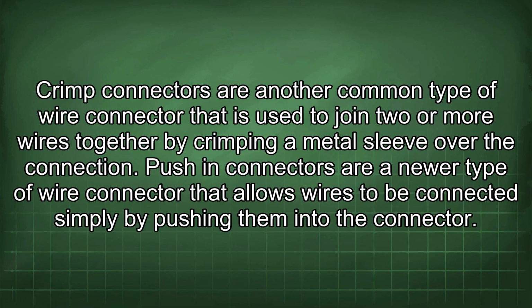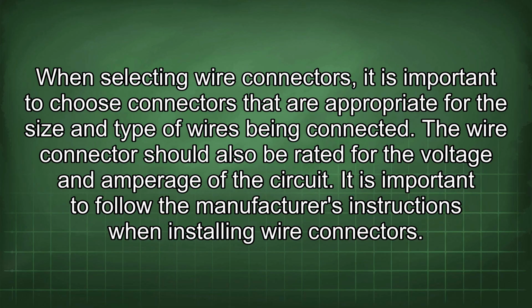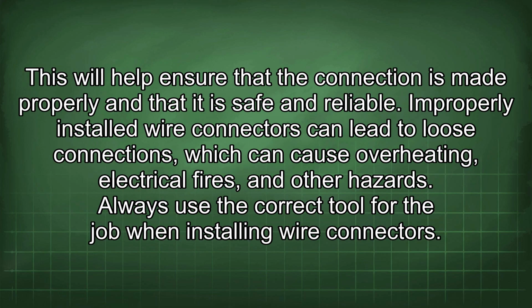When selecting wire connectors, it is important to choose connectors that are appropriate for the size and type of wires being connected. The wire connector should also be rated for the voltage and amperage of the circuit. It is important to follow the manufacturer's instructions when installing wire connectors. This will help ensure that the connection is made properly and that it is safe and reliable. Improperly installed wire connectors can lead to loose connections, which can cause overheating, electrical fires, and other hazards.